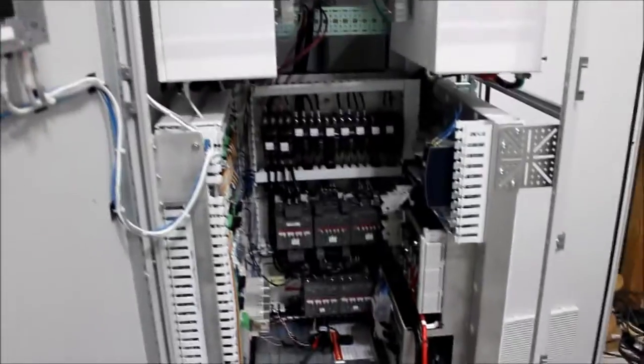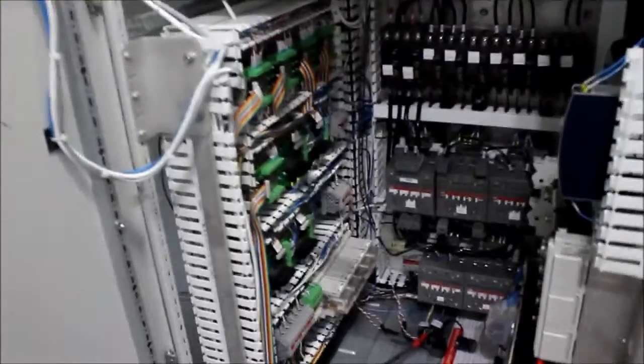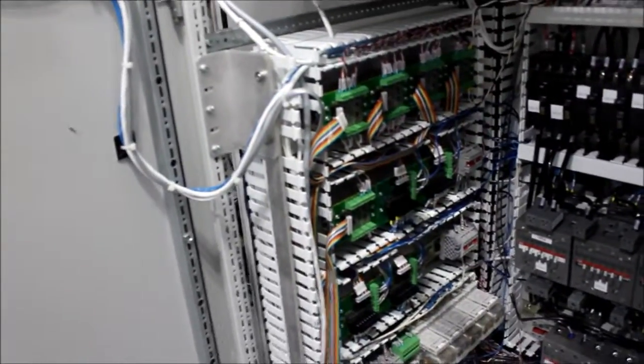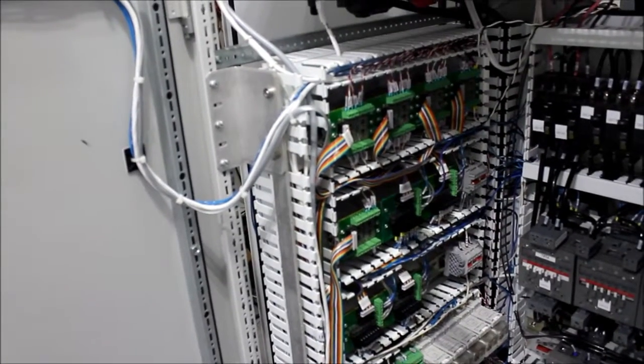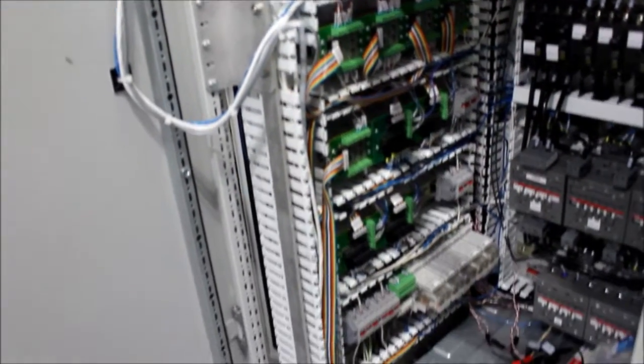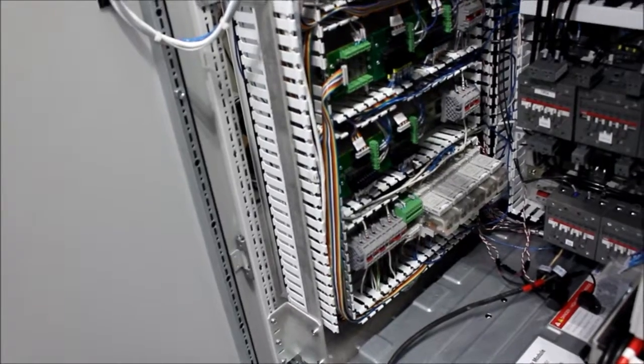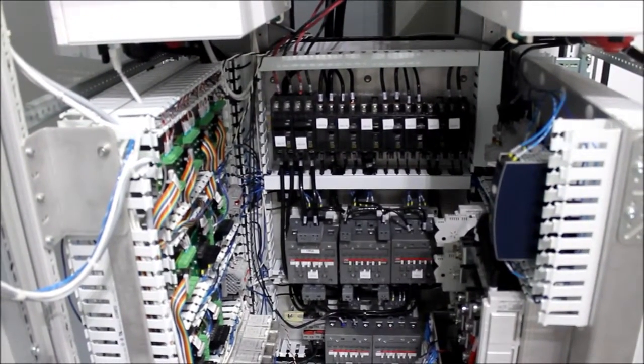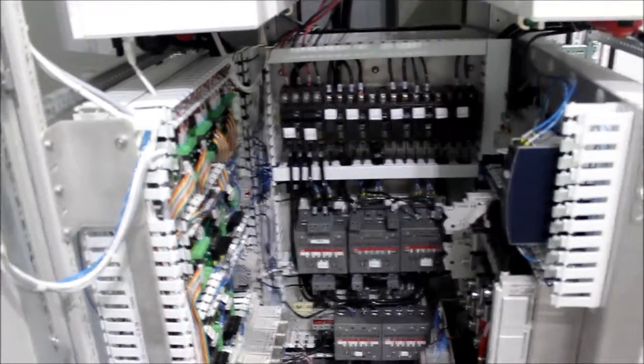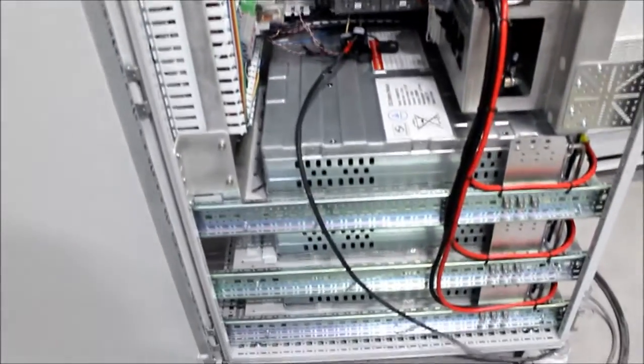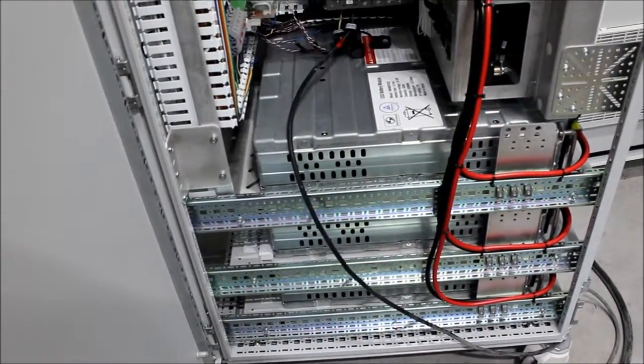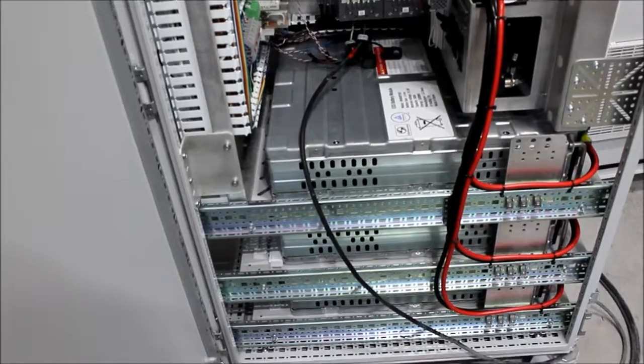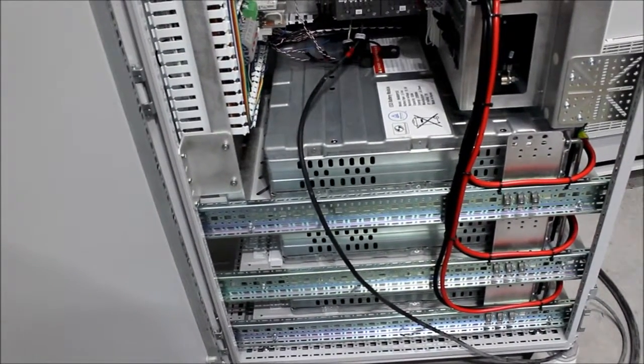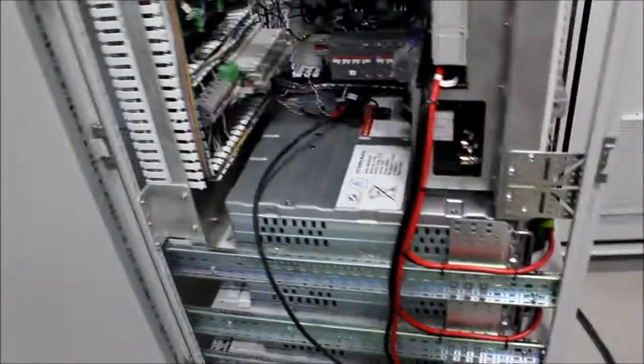Inside the system are the relay drive cards, the current monitoring, current transducer cards, fusing and load control and mode control relays, and circuit breakers for safety and protection. At the bottom are the 3 LG battery systems with 9.6 kilowatt hours of total storage.